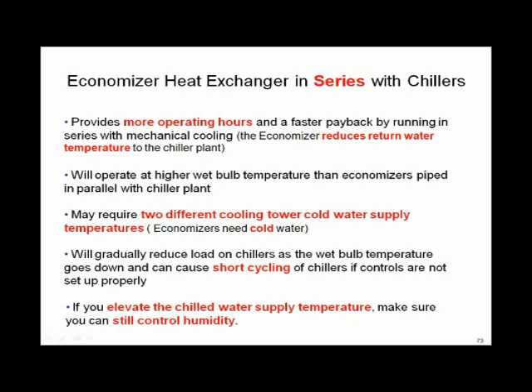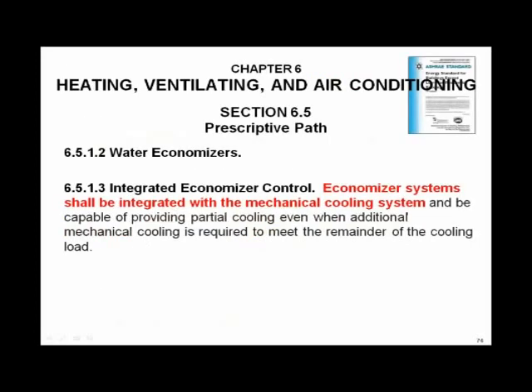In other words, can we take this 45 degree water and raise the temperature in the wintertime to a higher number and still keep everybody happy? The higher the supply water temperature in the wintertime, the more hours of operation the water side economizer has. Your limitation, you still got to maintain humidity control. So there's your limitation. Just be aware, you're going to see a lot more discussion on that, and you need to be thinking about it.